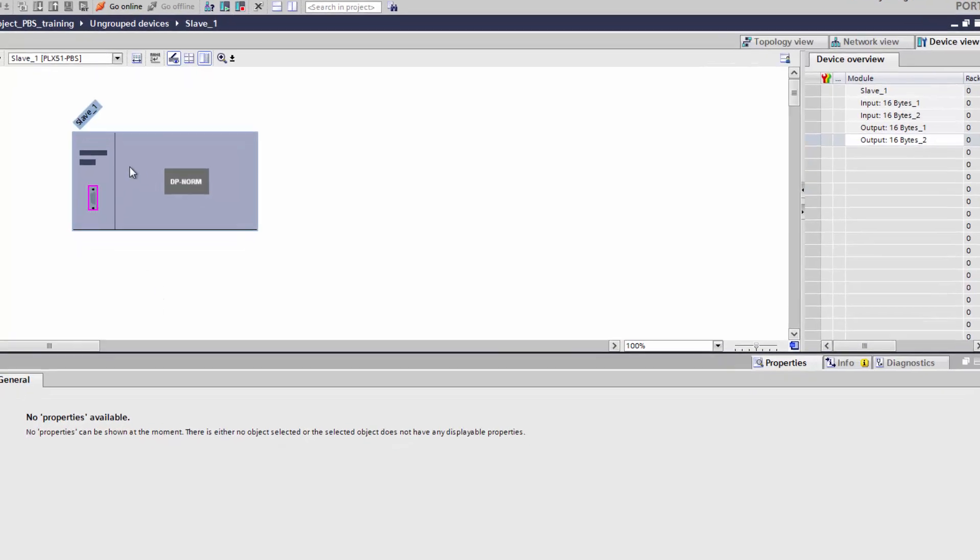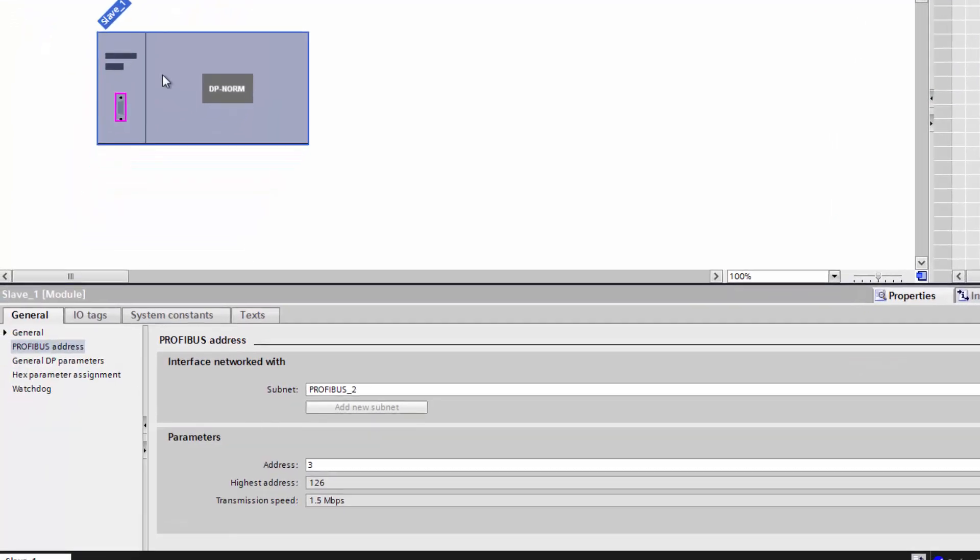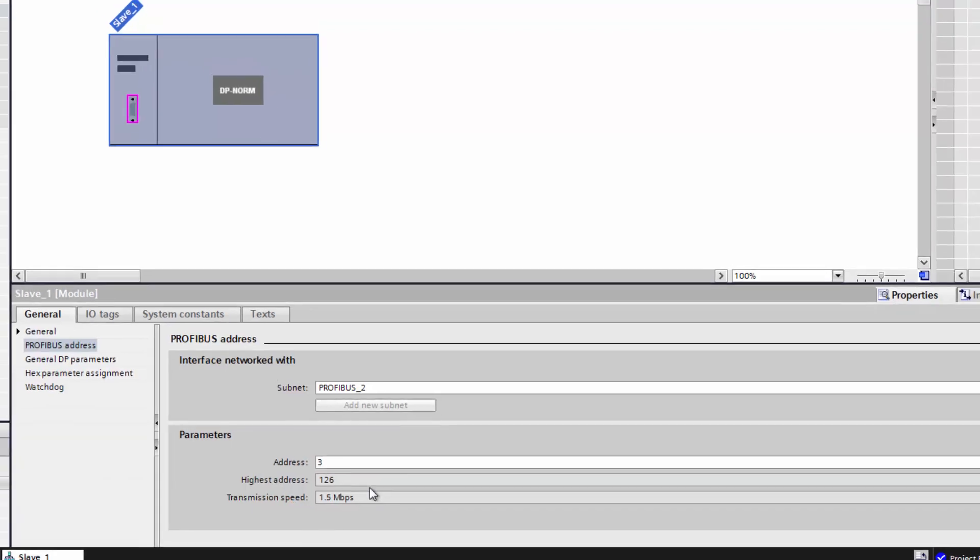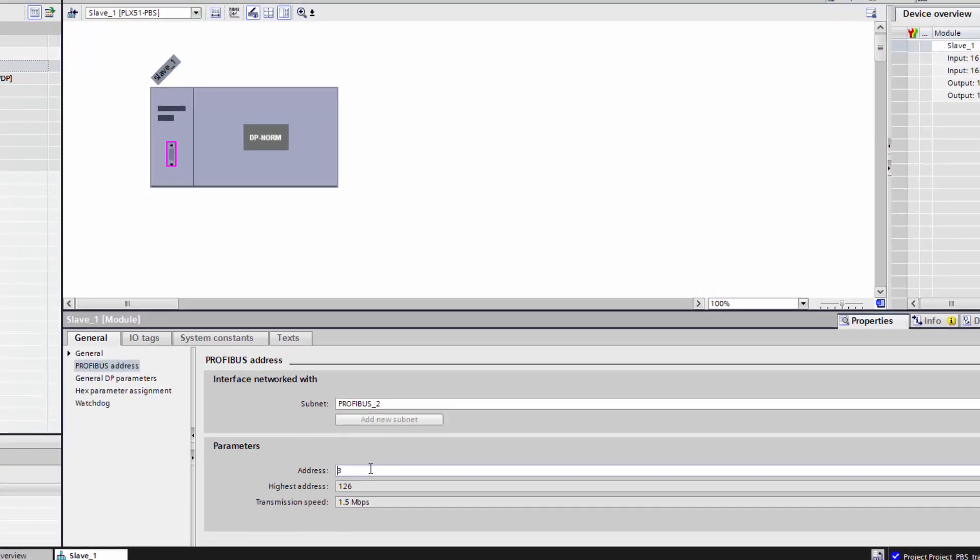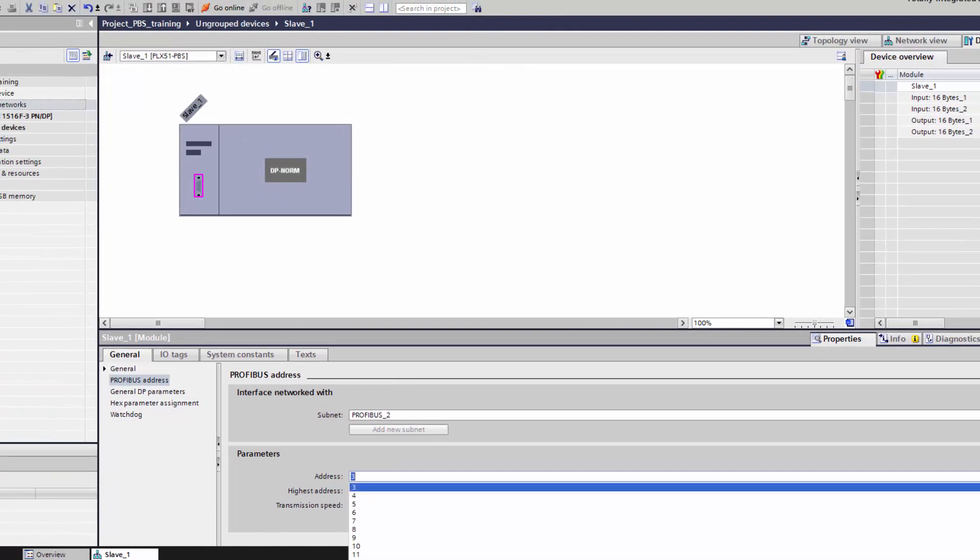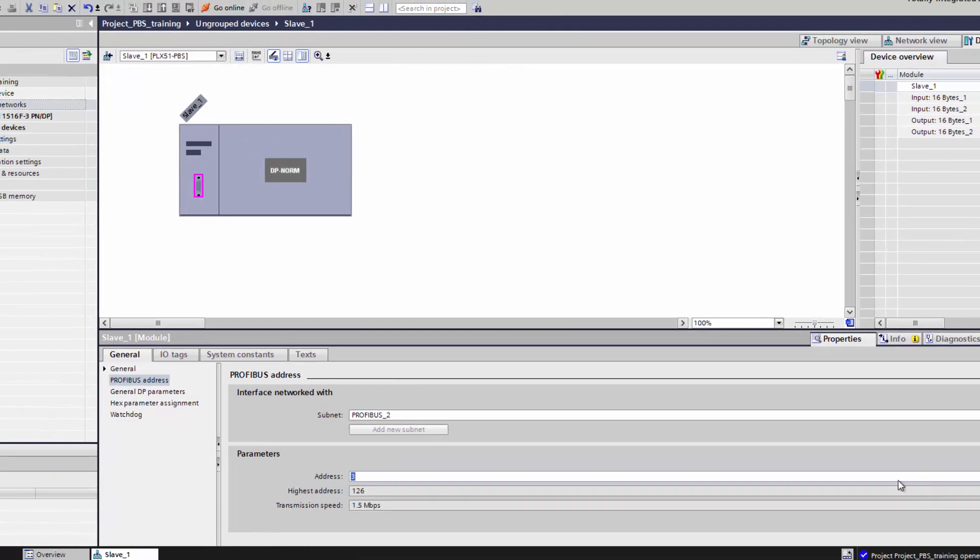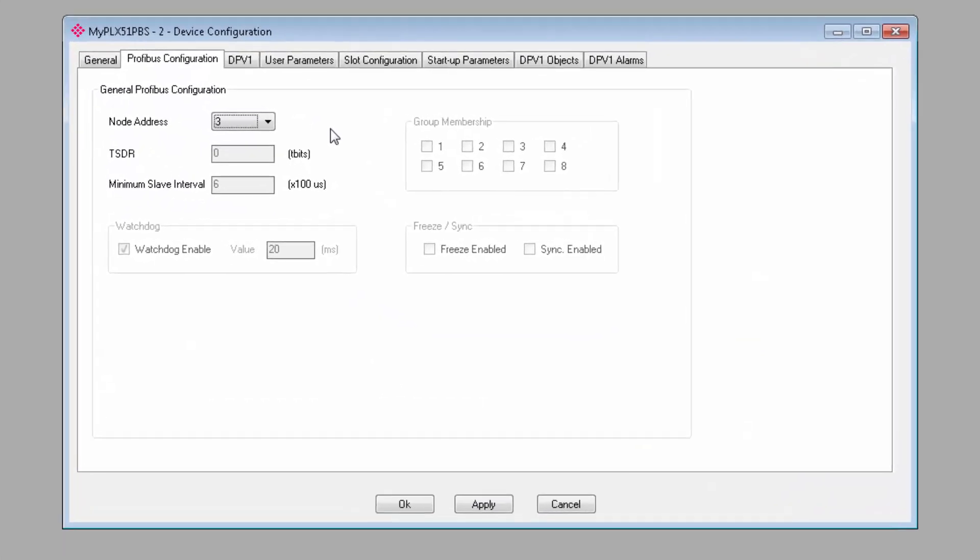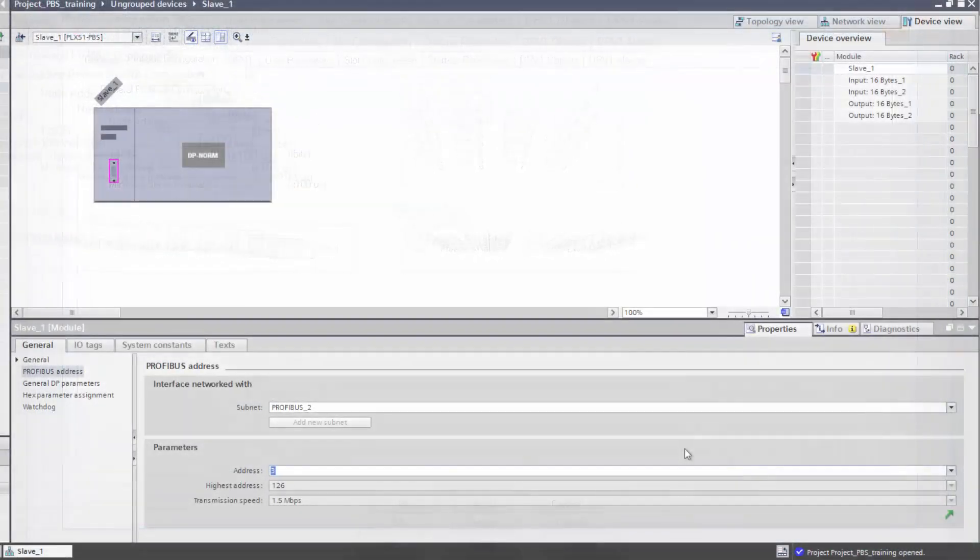and still in the device view, if you click on the slave and look under the general PROFIBUS parameters, you can see the node address, highest address, and transmission speed for the device. Now you can change the address, but the rest are determined by the master. So just be sure that what you have in the configuration utility matches what you're seeing here.